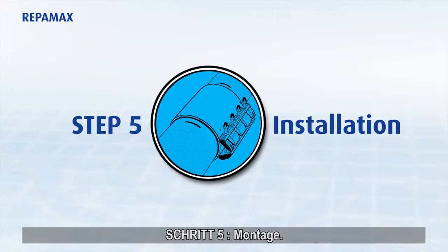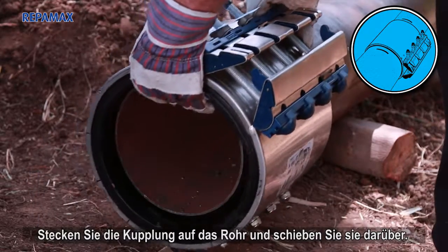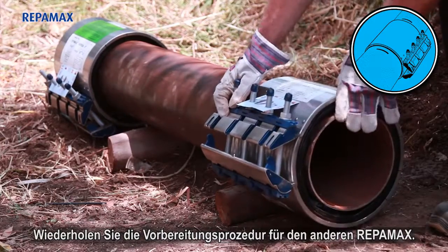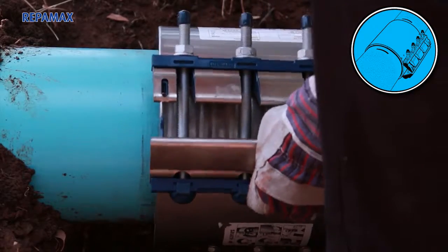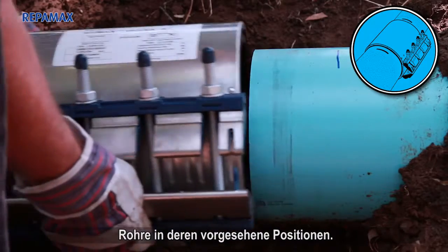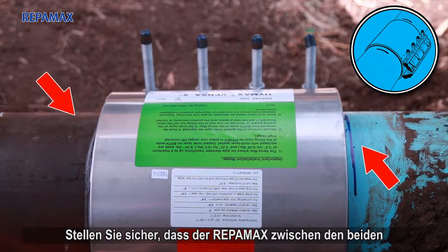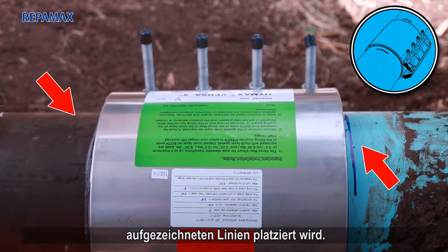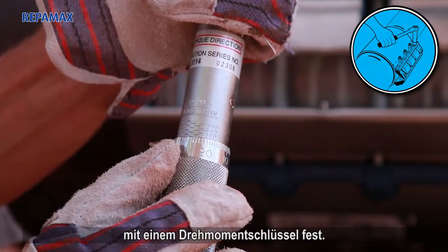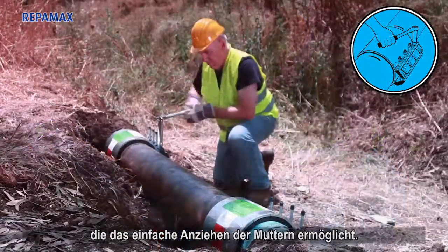Step 5: Installation. Stab the coupling onto the pipe and slide it over. Repeat the preparation procedure with the other REPAMAX. Bring in the replacement pipe section and slide both pipes to their proper positions. Make sure that the REPAMAX is placed between the two marked lines. Tighten the bolts according to the specified torque using a torque wrench. Place the locking mechanism in a position that allows easy tightening of the nuts.